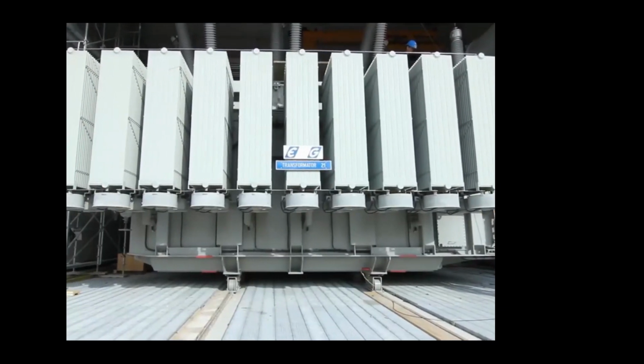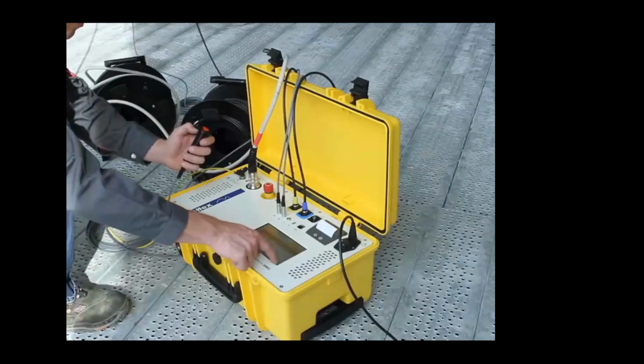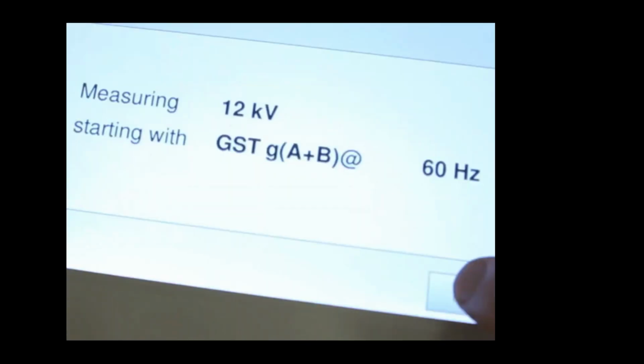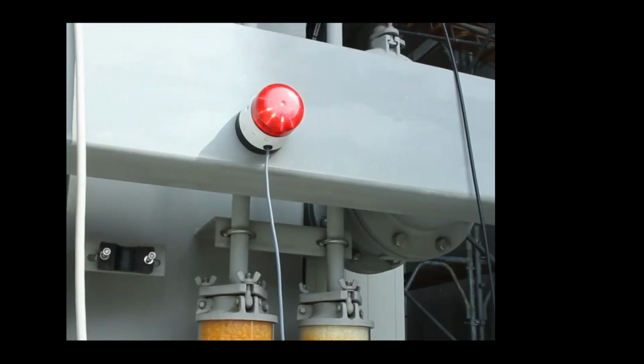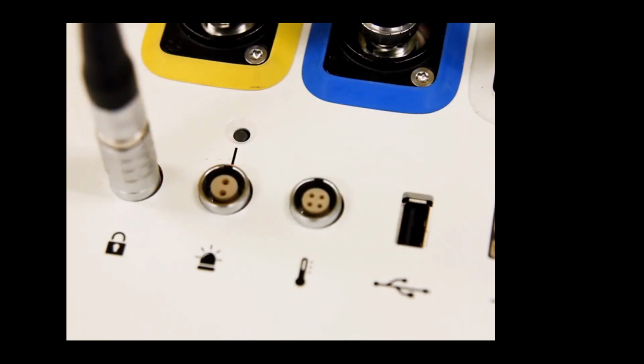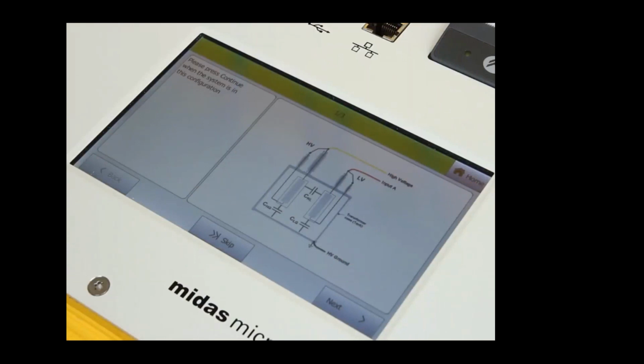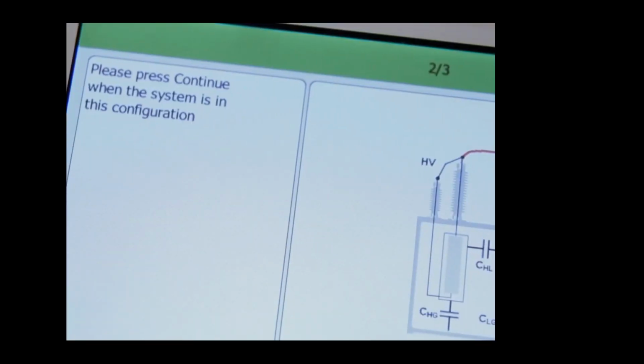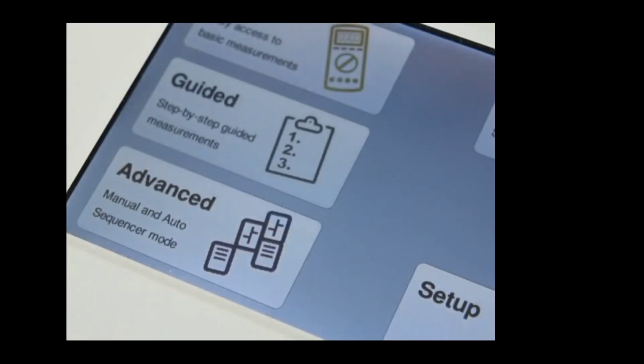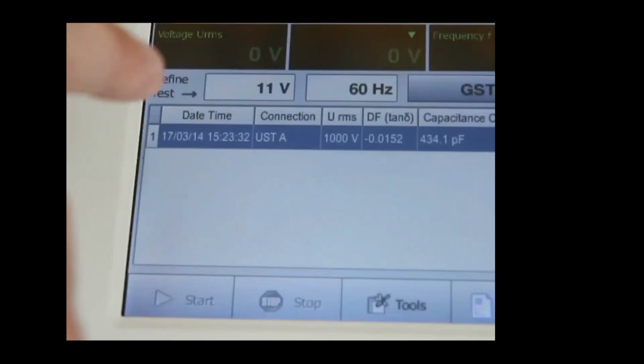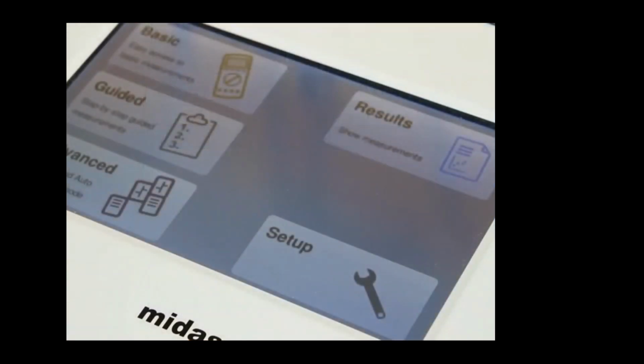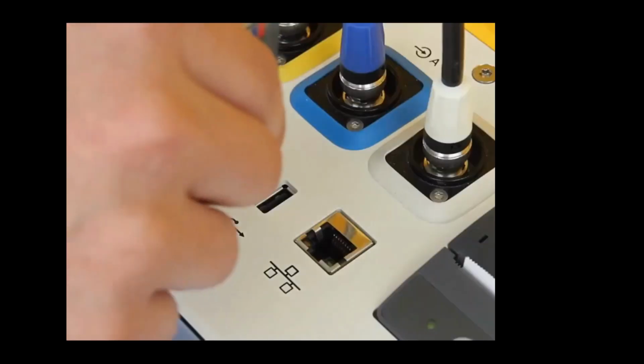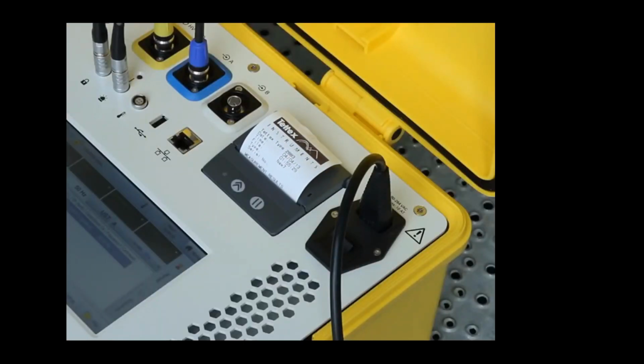Before starting the test, check that your test area is free of any hazards. Then, hold down the safety switch and click the high voltage on button. Note that the warning light turns on when high voltage is engaged. This is for added safety to both the operator and others in the area. After each measurement, the MIDAS Micro will prompt the user to confirm all connections to the device under test for the next measurement. Advanced mode is also available for users that want to create a custom sequence or have a special application not covered in the guide and basic modes. After all tests are complete, results are displayed in either numerical or graphical form. By using our data acquisition software, users have the option to save the results via USB or print the results with the integrated thermal printer.